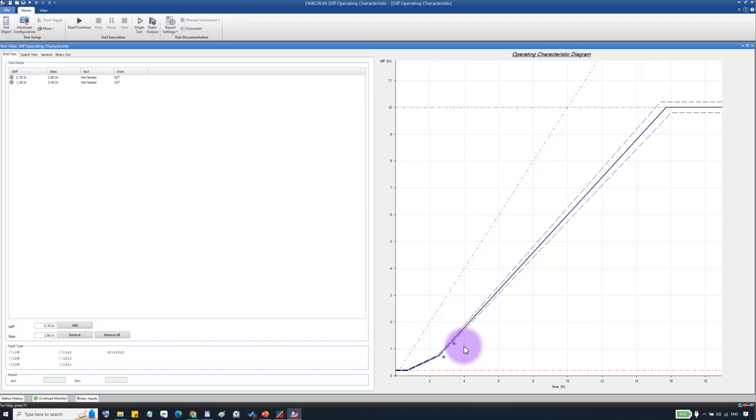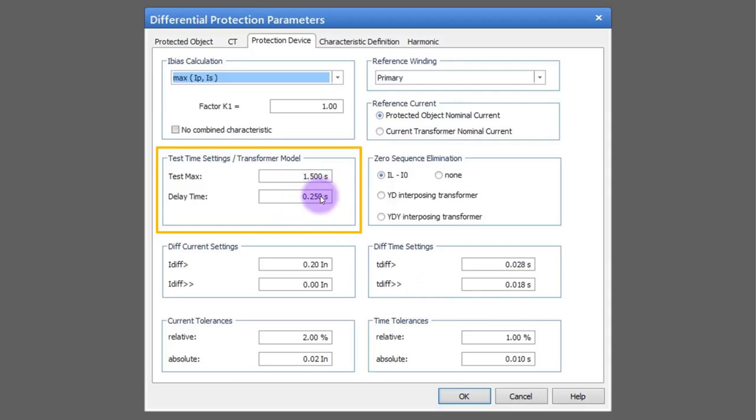The trip signal is not, for instance, 50 millisecond or 20 millisecond. It should be, for instance, 200 millisecond. That is why the signals are available even if there is no current in the relay. So we have to wait for some time. That is the point, and we have to set these parameters.